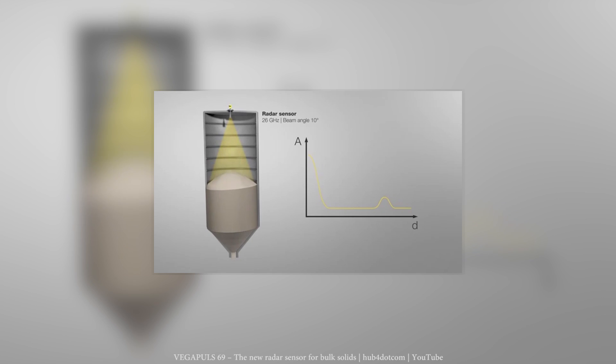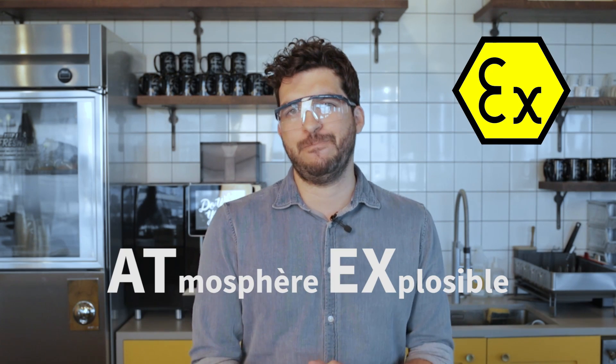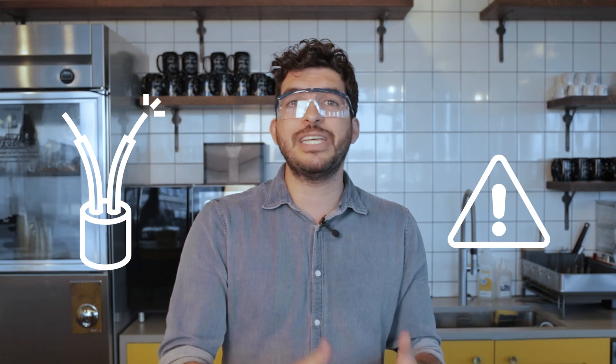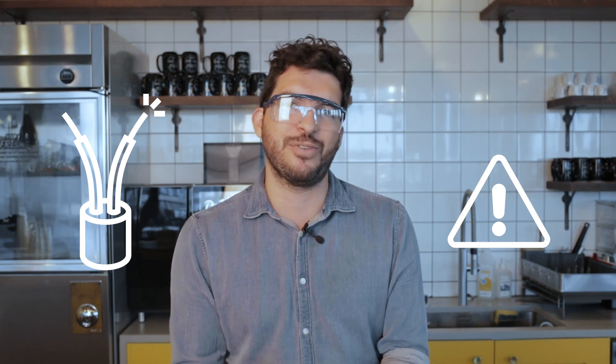Now imagine you go to a milk powder production plant and you need to measure the level on a storage silo. In this case the level measurement should comply with a European directive known as ATEX. In the case of milk and other dust storage facilities, instruments should be intrinsically safe, or Ex i. This means that the instrument will not become an ignition source or will not heat up to a temperature that could ignite the surrounding explosive atmosphere.